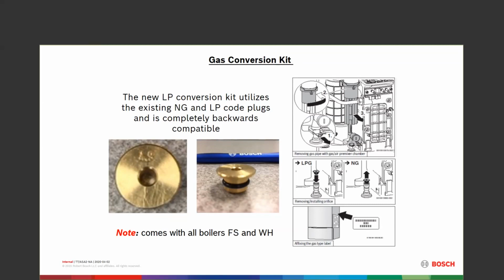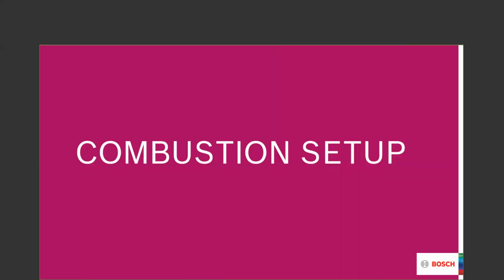If you do not have it, the throttle that you're going to adjust for high fire will actually be adjusted as an orifice. It's an adjustable orifice. That's all that is. It adjusts gas volume. So our gas valve adjusts gas pressure, and our gas throttle adjusts volume. So you don't have to have it, but it certainly makes life a lot easier with that.